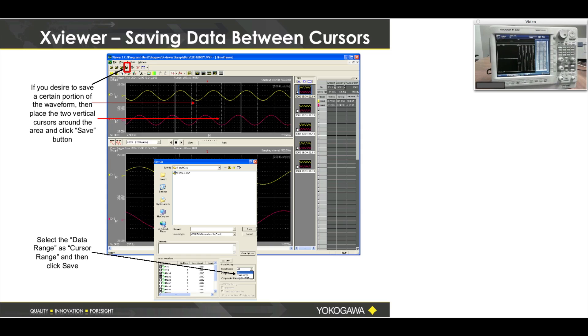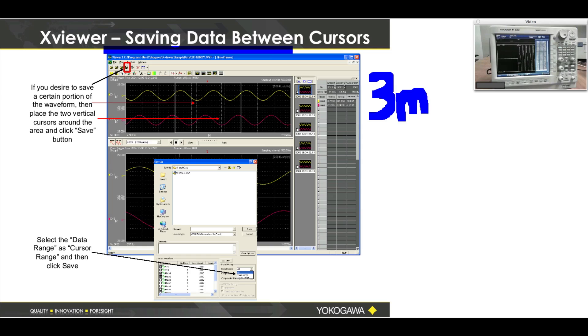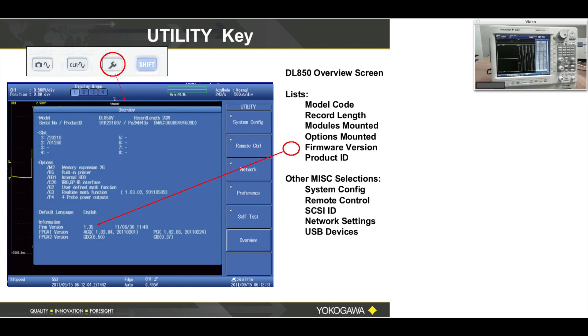If you need to reduce your data — say you have a three-day recording but only want three minutes — you can choose file, then save as, then more options, and set the data range simply to the cursor. You can save zoom only or cursor only. We do about three firmware upgrades a year and those often add new features, so make sure you get the latest firmware.